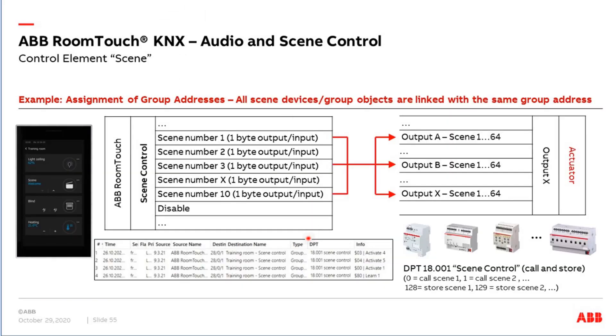For linking group addresses for scenes, it's not really difficult — we need only one group address, because with one group address we can call up to 64 different scenes. We get the objects: scene number one, two, three, up to ten. We create one group address and link it to all our scenes, then send it to the actuators — switch actuator, dim actuator, DALI gateway, etc. We link the group address to the scene objects like Output A, Output B, Output D, and so on. Only one single group address is needed.